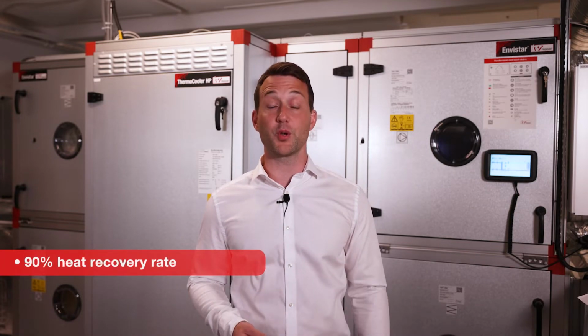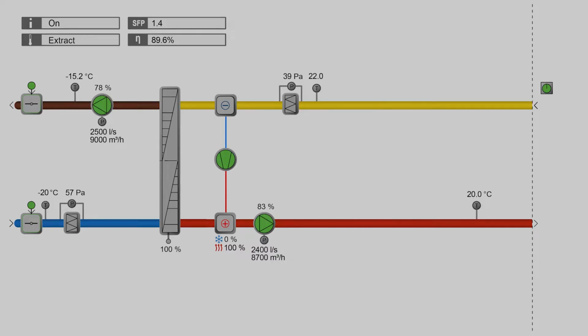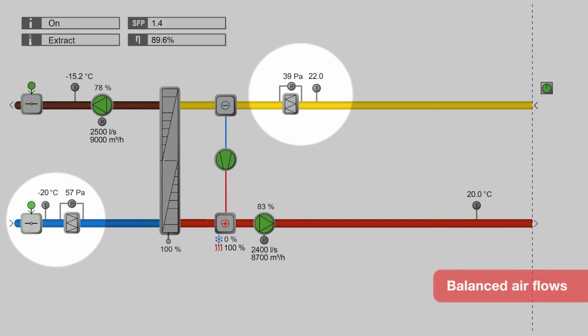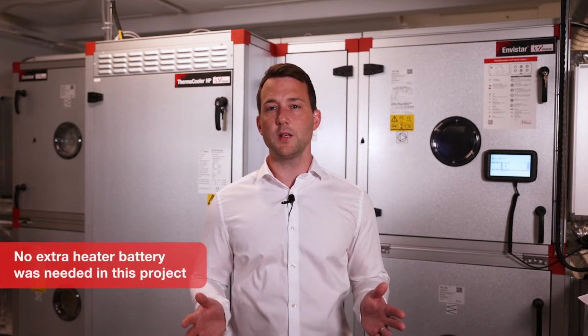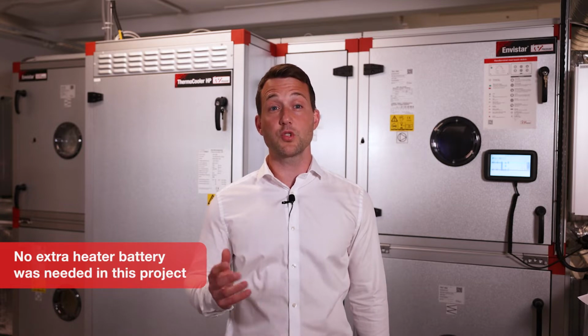The combination of rotary heat exchanger working with the Thermocooler HP means we can achieve a heat recovery rate of about 90%, which results in a very energy efficient ventilation solution. At 22 degrees in the extract air and minus 20 degrees outdoors, we can constantly maintain 20 degrees in the supply air. The main heating of these premises takes place via radiators, which in this building are connected to district heating. Thanks to the highly efficient thermal wheel and the design of the heat pump, which means that it does not need a defrost cycle, there is no need for any extra heater battery, which is usually located in the supply air side.